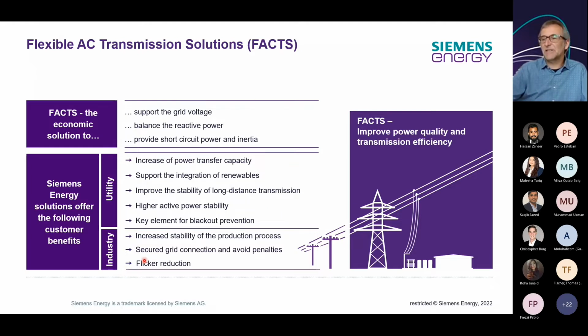If you talk about the industry where FACTS devices are used, one example is that you want to have the production process stable. You don't want any interruption caused by instability of the grid. You want the grid in a state where the technical parameters are met, otherwise penalties are applied. For example, flicker reduction is an issue for steel plants, and you want to get rid of it.